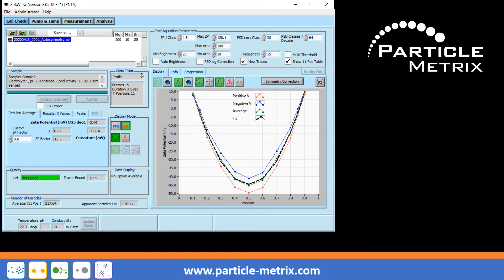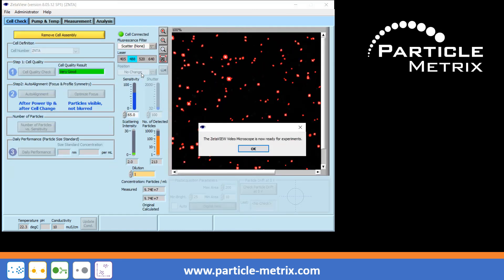If the parabola looks flat, inverted or jagged, the measuring cell must be cleaned. The ZetaView instrument is now ready for measurements.